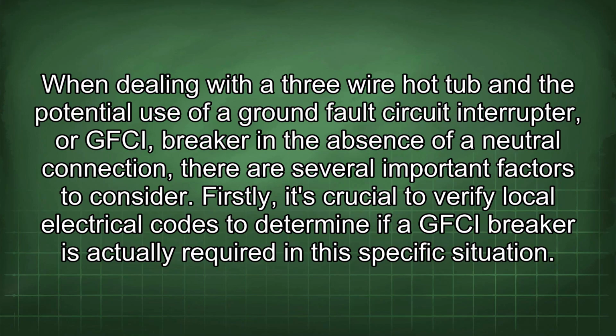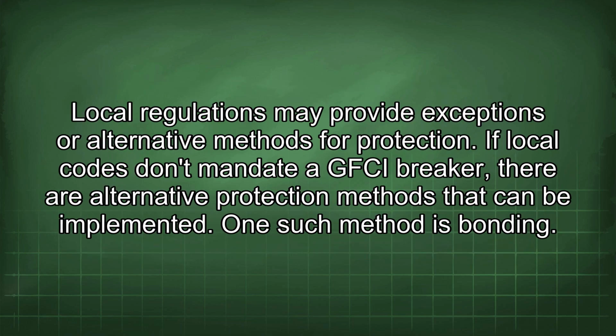When dealing with a 3-wire hot tub and the potential use of a ground fault circuit interrupter, or GFCI, breaker in the absence of a neutral connection, there are several important factors to consider. Firstly, it's crucial to verify local electrical codes to determine if a GFCI breaker is actually required in this specific situation. Local regulations may provide exceptions or alternative methods for protection. If local codes don't mandate a GFCI breaker, there are alternative protection methods that can be implemented.